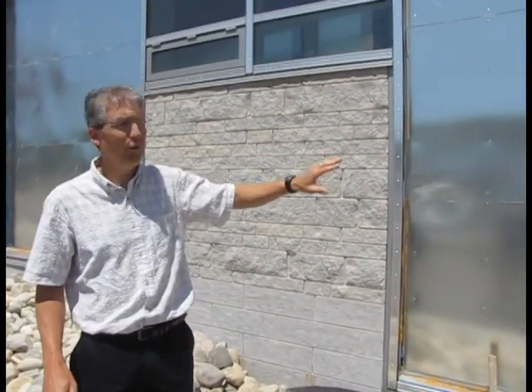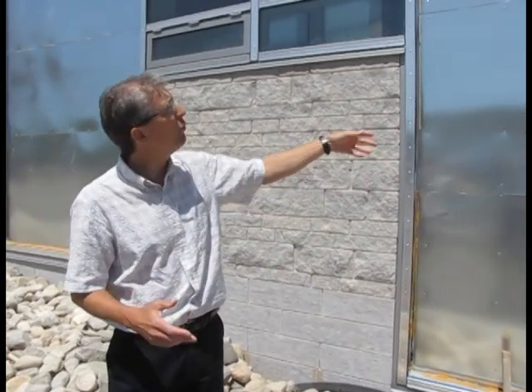Okay, we're outside now, the south wall of the building, and this is another part of the old school passive energy system. The big silver panels that you see behind me are part of our solar walls or solar chimneys, we call them. And they're not done yet. That's not what it'll look like. There will be a dark sheet of steel, dark blue, that's all perforated, that goes over top of these so that there's an open space behind them. That will heat up in the sun because of its dark color. And then as the heating system draws fresh air into the building through these walls and up into the heating system, the air is preheated. So again, it just lowers the loading that the actual heat pumps have to put in place to heat the air. So passive, cheap, efficient system.